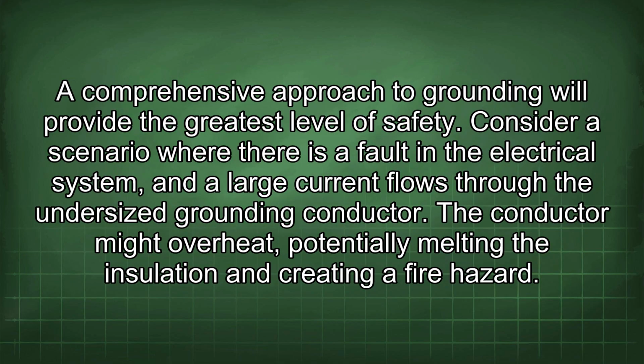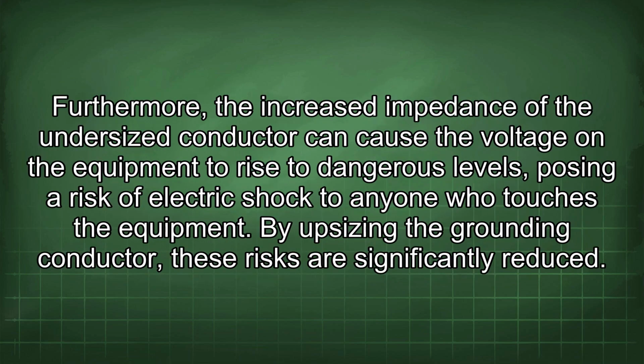A comprehensive approach to grounding will provide the greatest level of safety. Consider a scenario where there is a fault in the electrical system, and a large current flows through the undersized grounding conductor. The conductor might overheat, potentially melting the insulation and creating a fire hazard. Furthermore, the increased impedance of the undersized conductor can cause the voltage on the equipment to rise to dangerous levels, posing a risk of electric shock to anyone who touches the equipment.